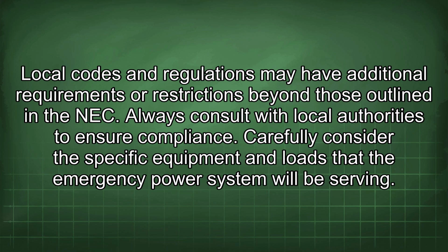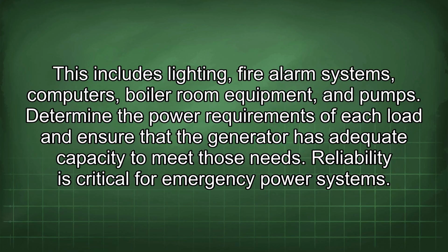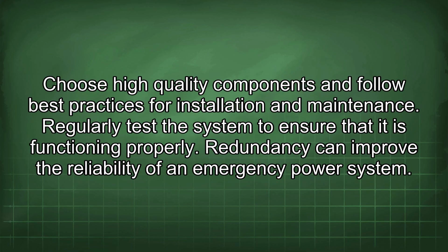Carefully consider the specific equipment and loads that the emergency power system will be serving. This includes lighting, fire alarm systems, computers, boiler room equipment, and pumps. Determine the power requirements of each load and ensure that the generator has adequate capacity to meet those needs. Reliability is critical for emergency power systems. Choose high-quality components and follow best practices for installation and maintenance. Regularly test the system to ensure that it is functioning properly.